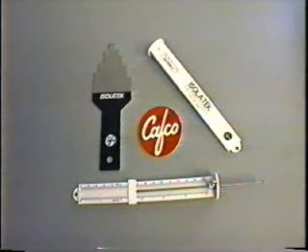Thickness checks should be randomly taken in order to ensure that the sprayer doesn't exceed the required design thickness. The following are recommended thickness gauges for CAFCO wet mix materials. Excessive thickness may result in delamination or prolonged drying time and is the most common reason for reduced yield. Flutes must be filled or plugged depending on the design requirement. This area is typically filled in and then sealed by a returning pass that also hits the top flange tip.